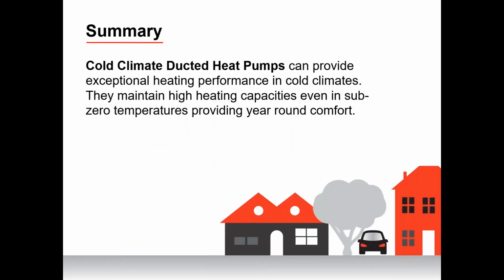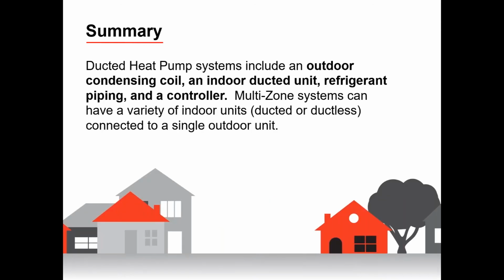In summary, we banged through that pretty easy. Cold climate ducted heat pumps can provide exceptional heating performance in cold climates. They maintain high heating capacities even in sub-zero temperatures, providing year-round comfort. We looked at those cold climate heat pump charts. That is consistent with these cold climate heat pump systems. It's high capacity at deep negative temperatures. So a lot of times we think, oh, I need backup in Indianapolis. Well, maybe you don't. Let's look at your design temp. Let's look at your heating load. Maybe you don't need backup heat. Maybe the cold climate heat pump can act on its own.